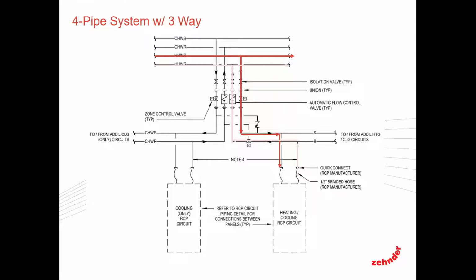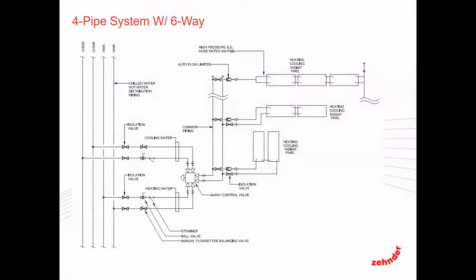And then in this case, I would have no hot water passing through the cooling only circuits. So that's one of the popular options I've seen over the years. The other one is utilizing 6-way valves. So in this example, you have your chilled water entering your 6-way valve and then going out to your loops.